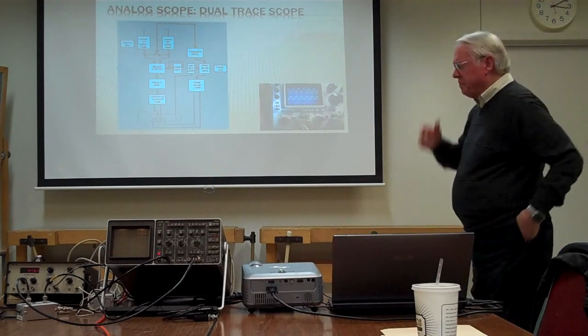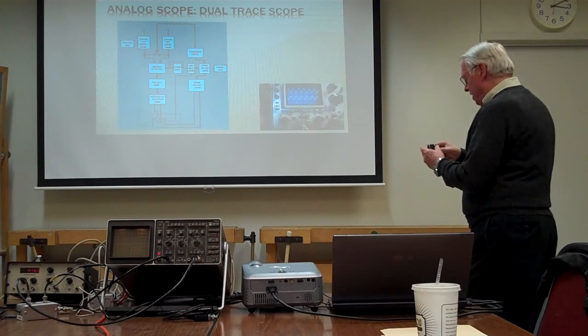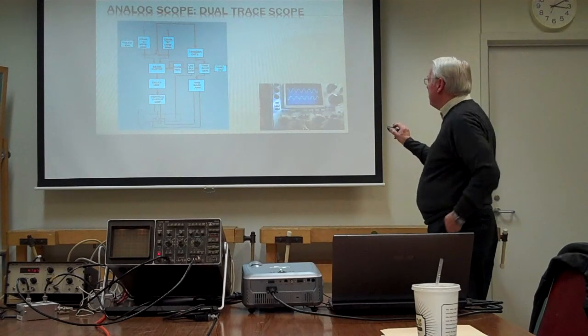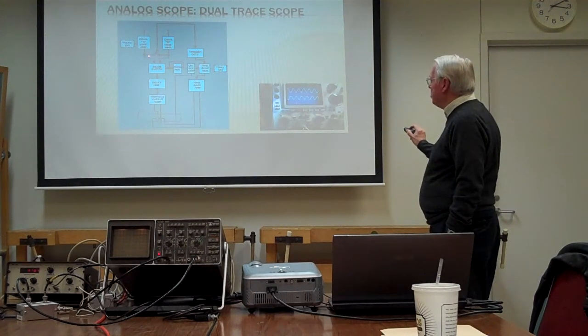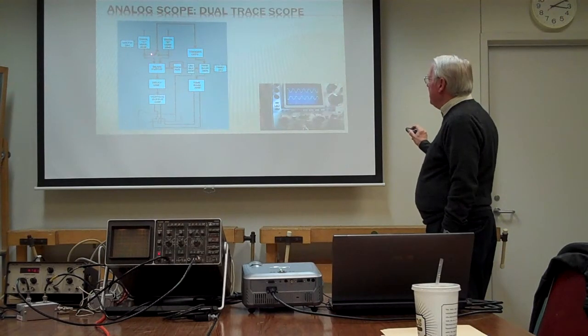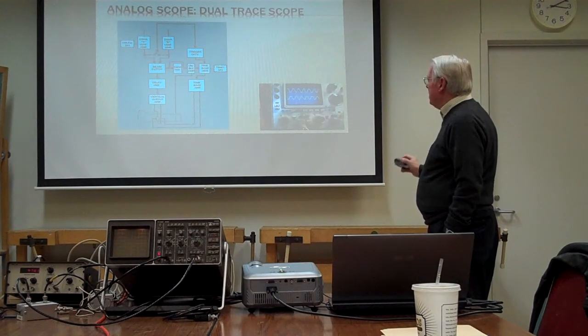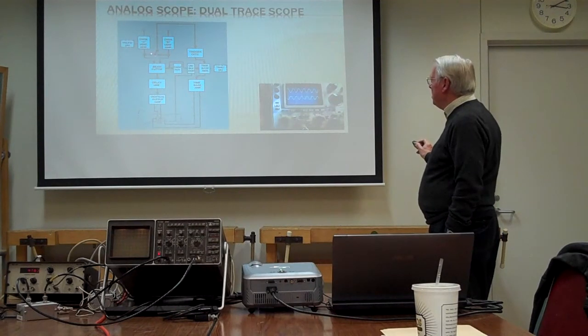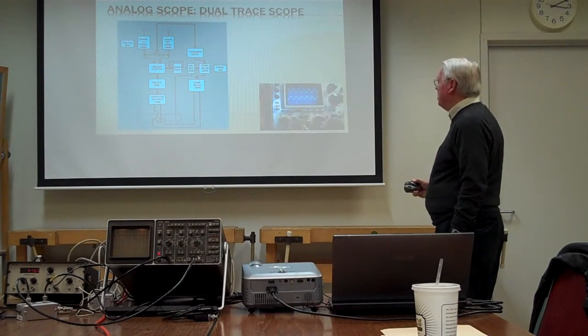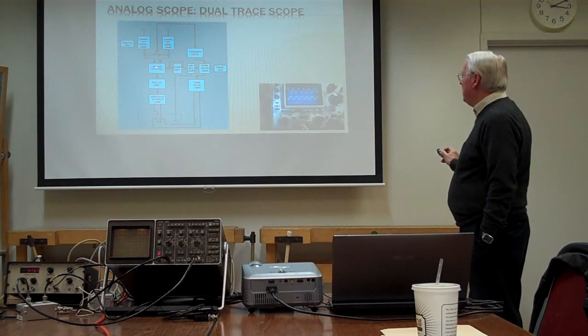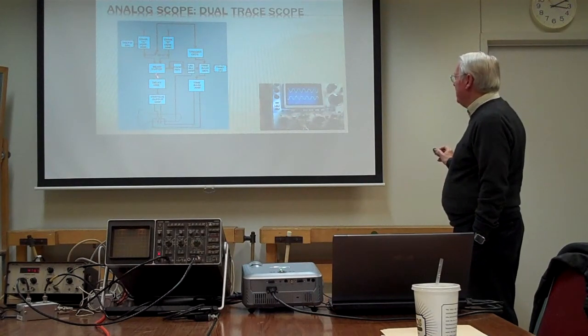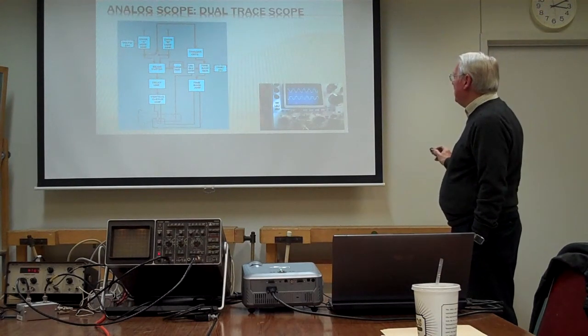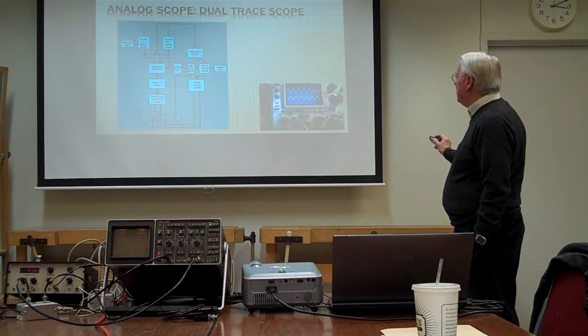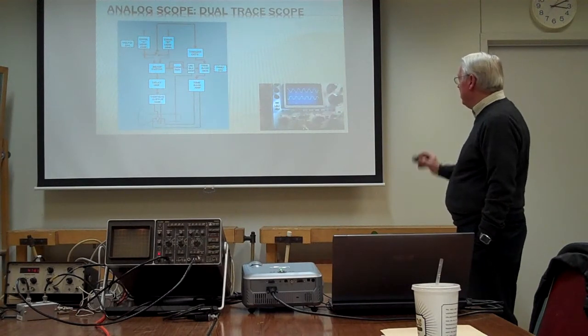Here's a picture of the block diagram, a little difficult to read, but you have input from channel A and input from channel B. There's a little switch shown here, and that switch is either in the alternate mode - not a switch you turn, but an electronic switch that jumps back and forth to switch the beam between the two. You also have a delay line, the vertical output, and a little chopper oscillator with an unblanking pulse, and you pull the triggering off of either channel A or channel B.